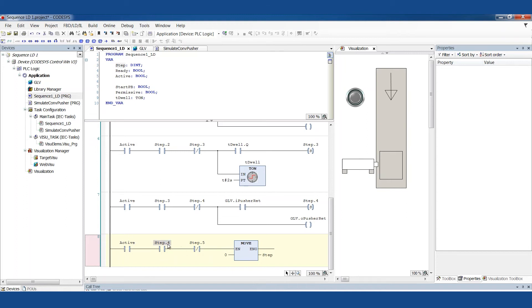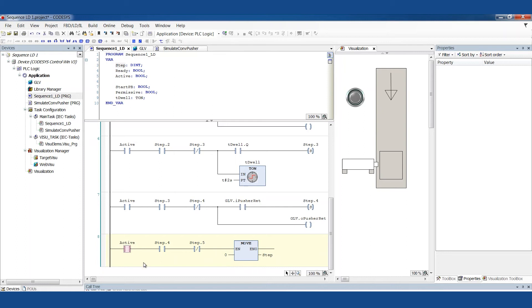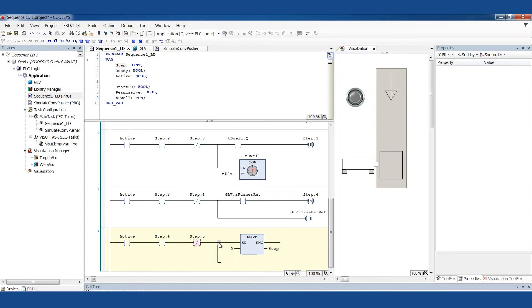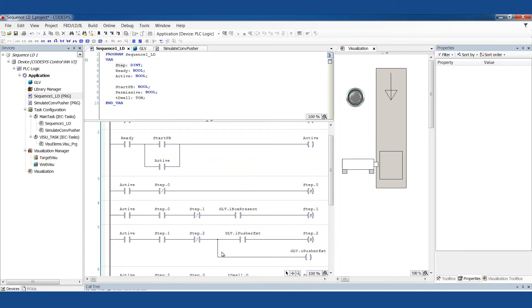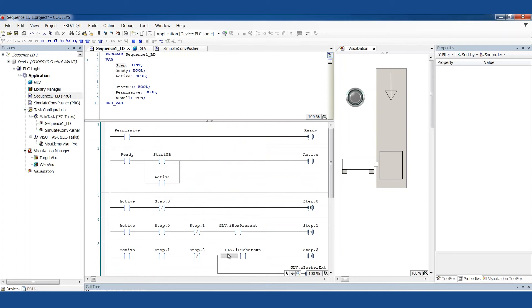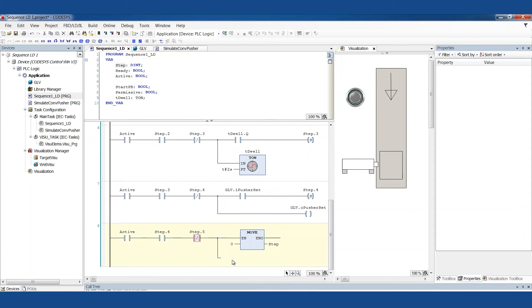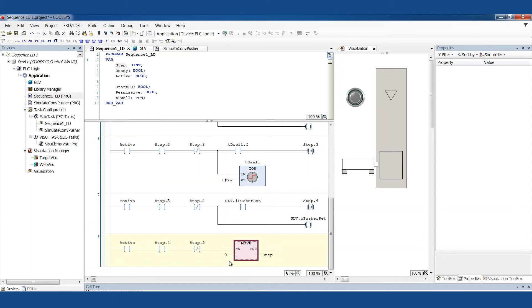The thing that I didn't do in this rung that I could have done and probably more often do do is set the active bit to false. Because right now, if this is running, we're in step four, this is active. By the way, there is no step five right now, so this really isn't necessary, but it's not hurting anything. It's just kind of a copy paste carry over. So I'm setting this to zero, I'm clearing it out, but I'm not telling it to stop running the sequence because this is still active. So I could also put another branch in here and turn active off. And if I were going to do that, then I would also want this active, instead of latching itself in, I would want this to be a set coil. And I would delete this active branch here, and then this would be a reset active.